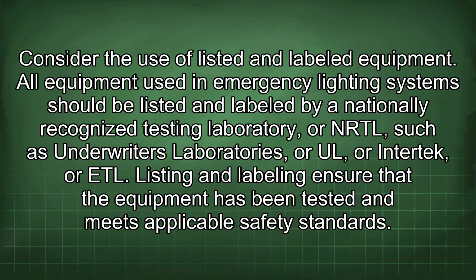Consider the use of listed and labeled equipment. All equipment used in emergency lighting systems should be listed and labeled by a nationally recognized testing laboratory, or NRTL, such as Underwriters Laboratories, or UL, or Intertek, or ETL. Listing and labeling ensure that the equipment has been tested and meets applicable safety standards.